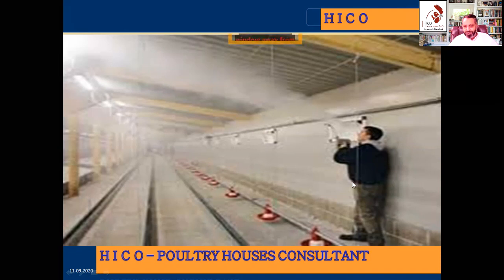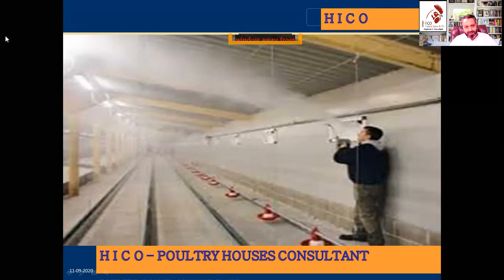In the smoke test, we use a smoke stick, mostly applied outside the house near the inlet. You can observe the air coming from the inlet at a desired air velocity of more than 100 feet per minute, entering centrally and then dropping. This is the main phenomenon of minimum ventilation.